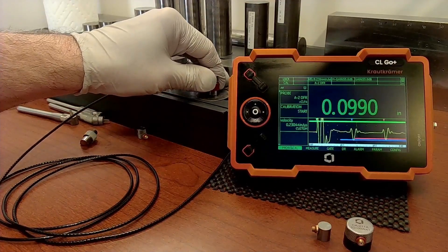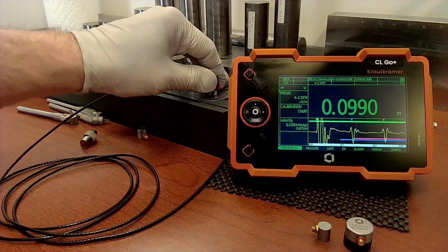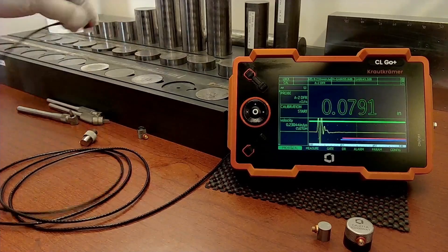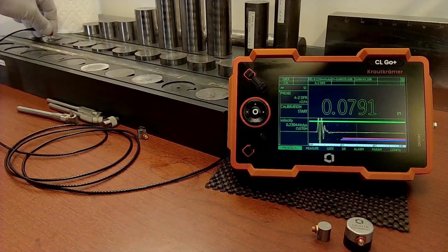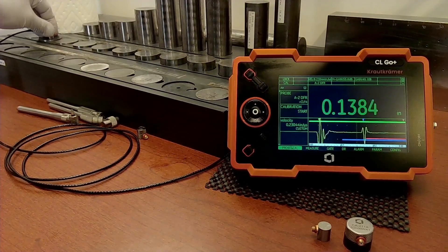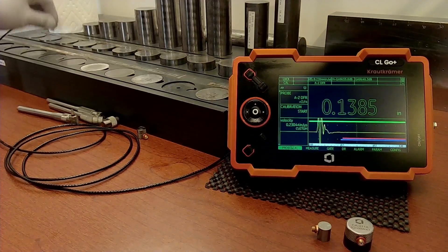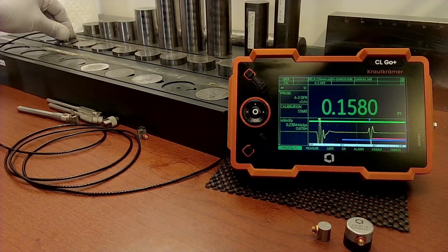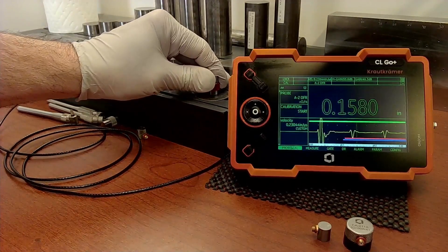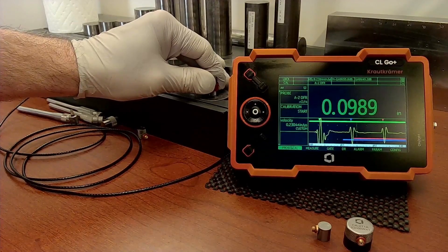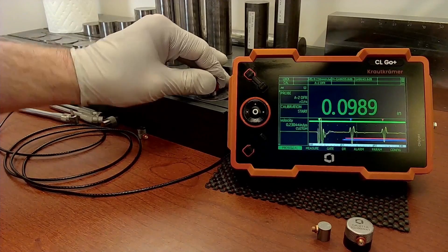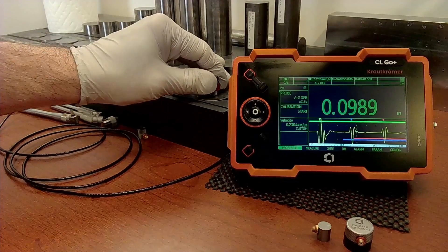And just that quickly we are calibrated. Go back to my 99 thousandths block and there we are. And now I can look at some different blocks. There's 79 thou. Go to a little bit thicker block. 138. So there's 158. So the instrument locks in on a reading very quickly and is very repeatable.